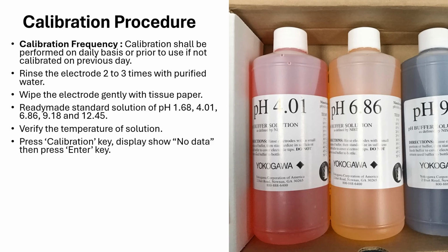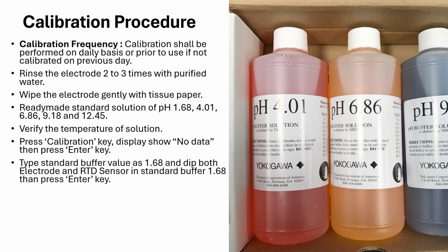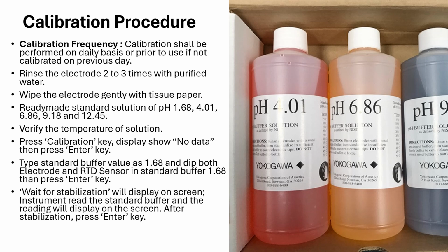Next, to start the calibration, press the calibration key. It will display no data, right? This indicates the pH meter is ready for calibration. When you see the no data on the display, press the enter key to proceed, right? Now the display will show enter value. Then type the value of the first standard buffer, that is 1.68. Then dip both the electrode and the RTD sensor into the pH 1.68 buffer solution and press enter, right? The display will now show wait for stabilization. The instrument is reading the standard buffer, and once stabilized, the reading will appear on the screen. Once the reading is stable, press enter to finalize this step. The calibration for this buffer is now completed, right?